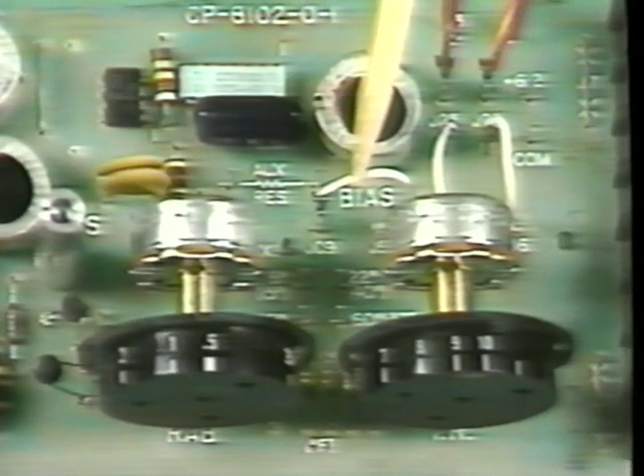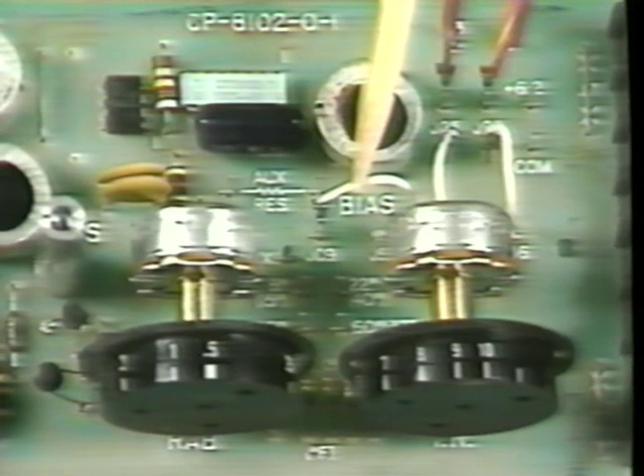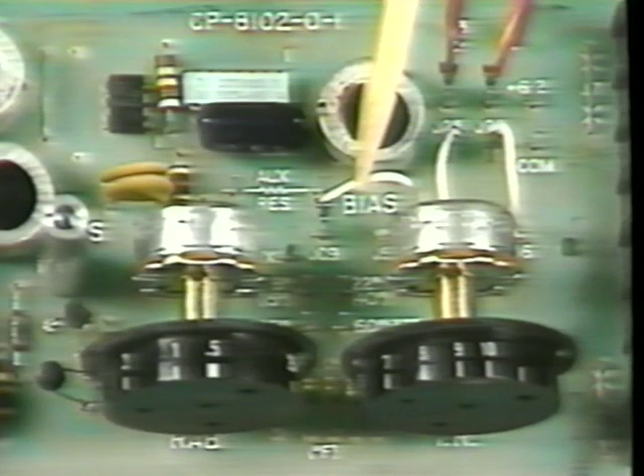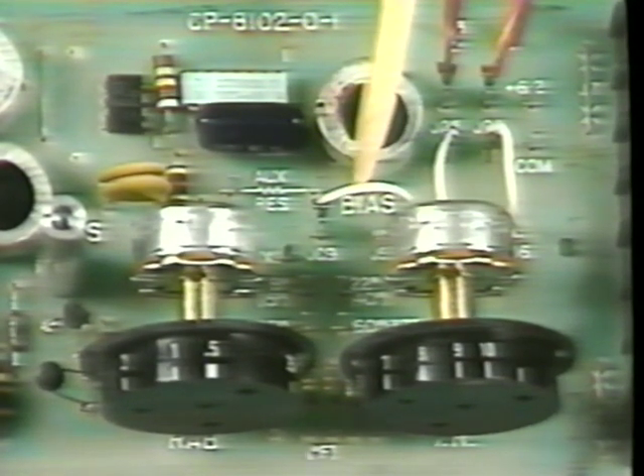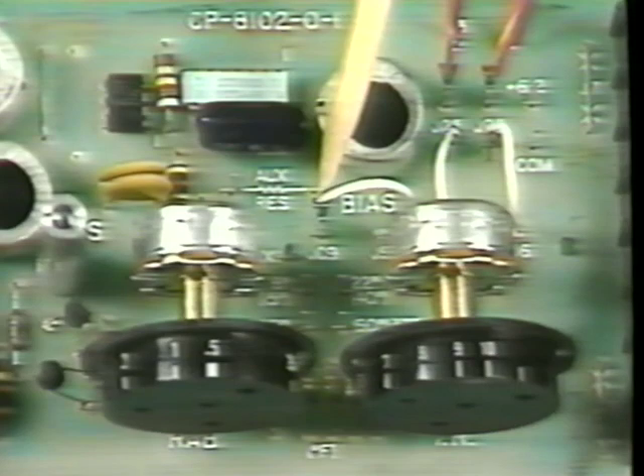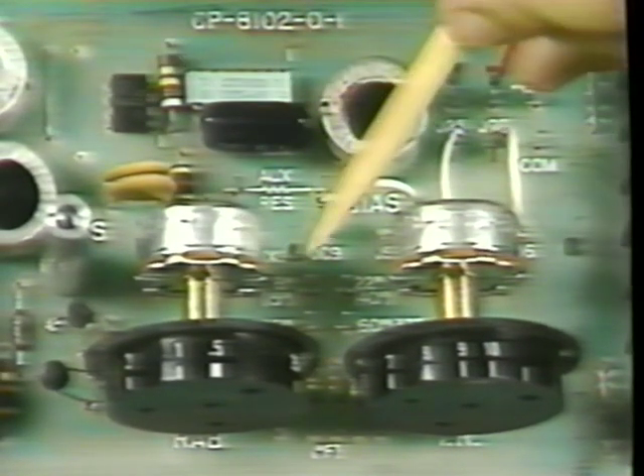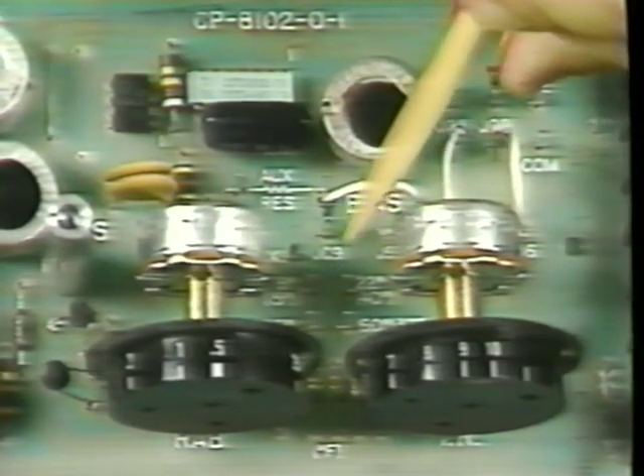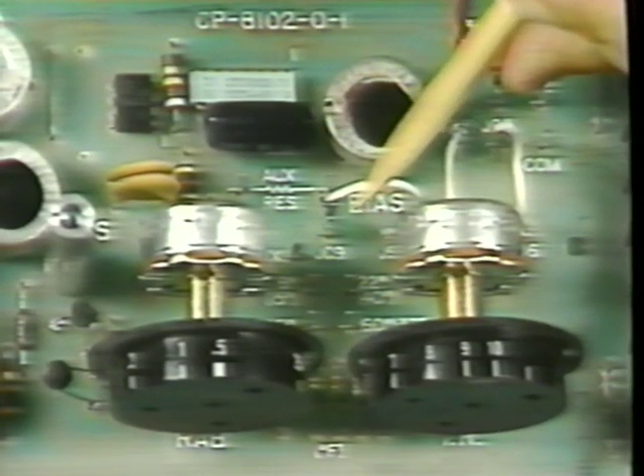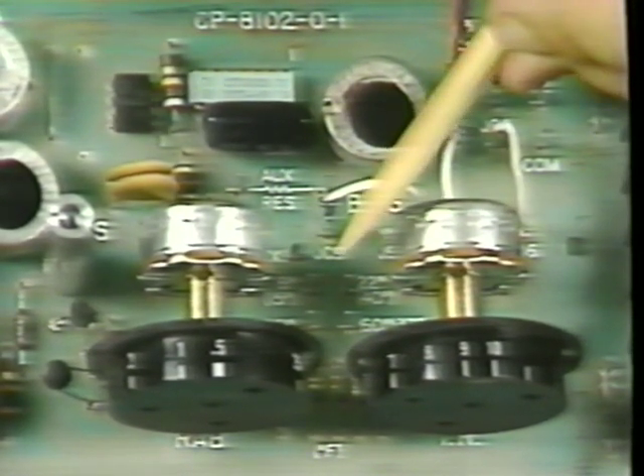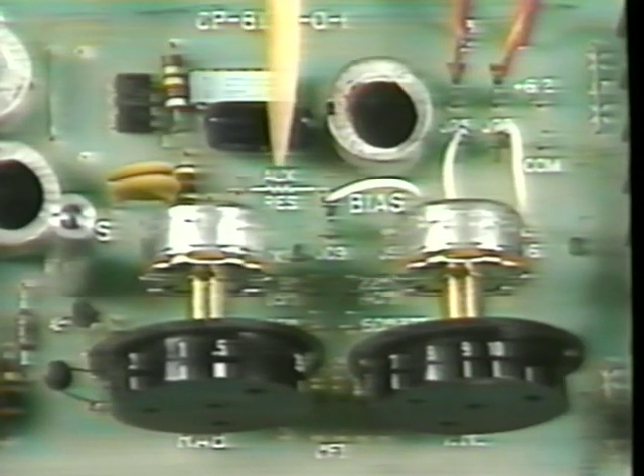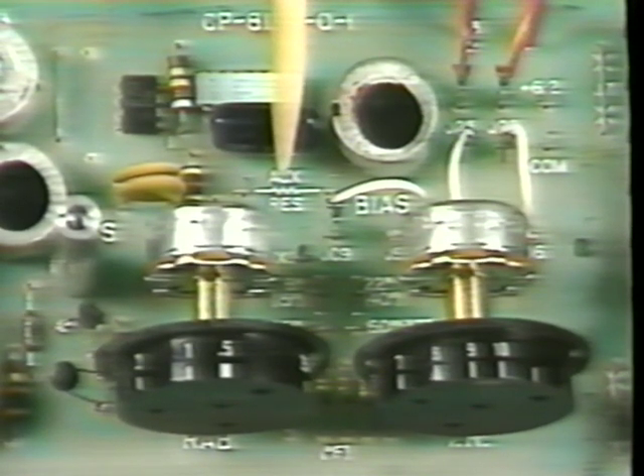Throttling range. While most applications will use a 2 to 10 degree throttling range, if a wider throttling range is desired, it is available through a fixed throttling range selection. By moving this jumper, jumper JC9, from its standard position to any one of these 4 pins, other wider throttling ranges can be selected. If none of these are suitable, an auxiliary resistor may be placed here and other throttling ranges achieved.